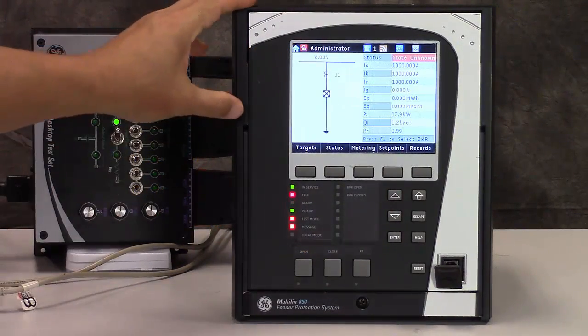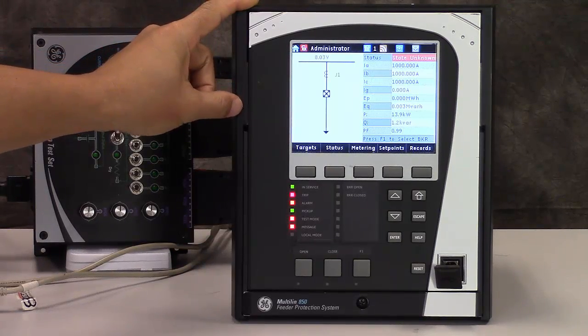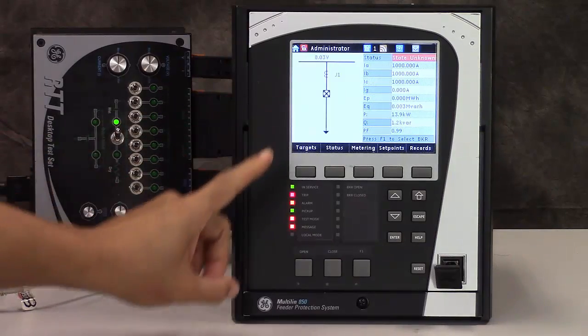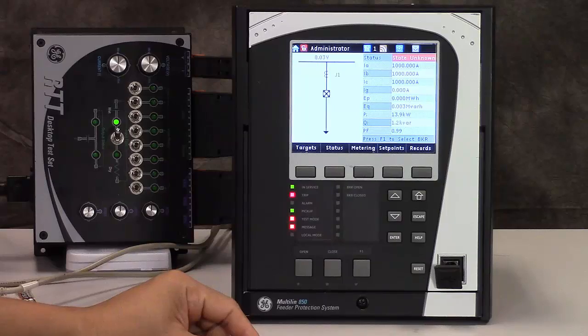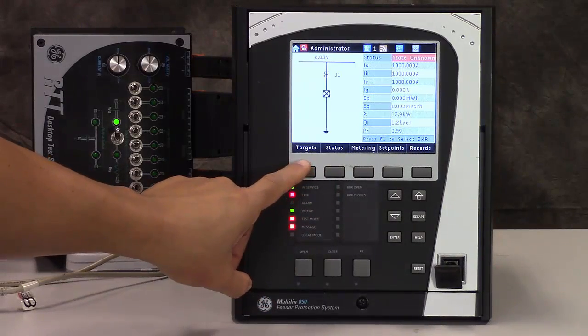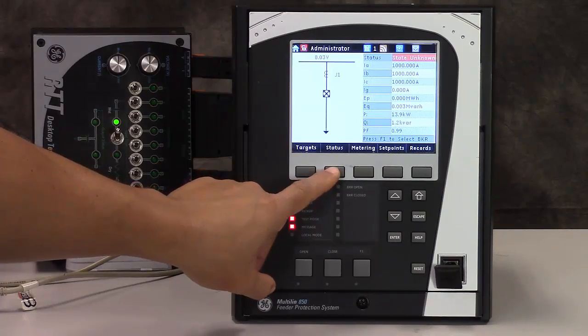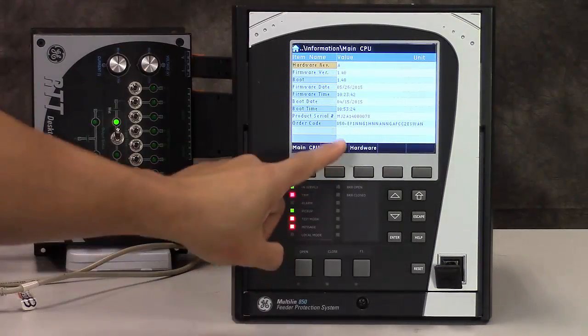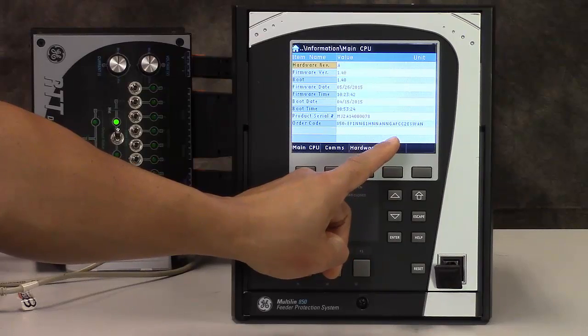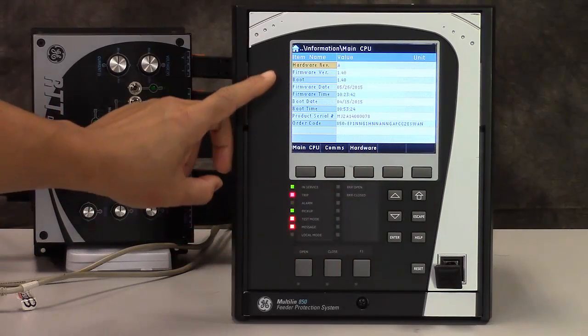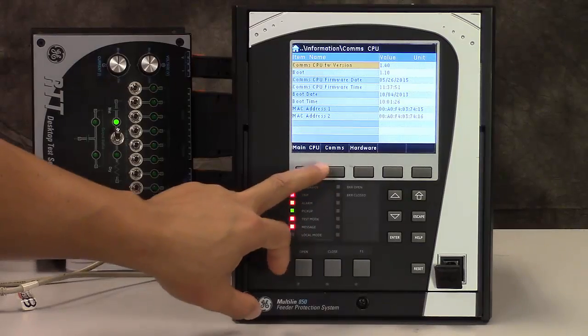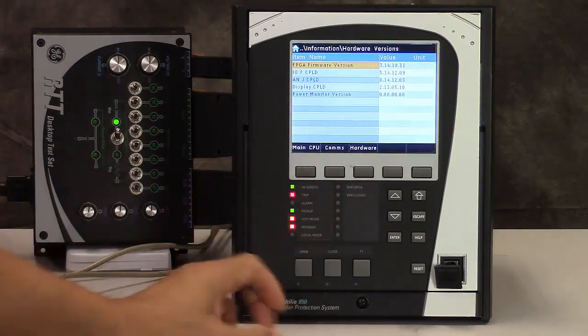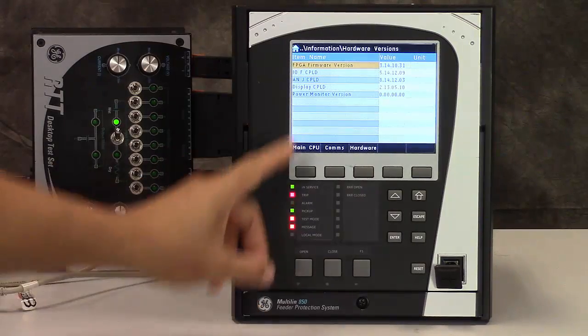Now we're going to explore the front panel of the 850 relays. From the front panel we can see the single line diagram and the metered current of the three phases. And at the bottom we've got the soft keys. We can check the firmware version by going to status, info, and we can know that this is the 850 relay. Secondary CT is 1 amp, and this has order code 2E, which means GOOSE messaging, 61850, is enabled. We can also know this firmware version is 1.4, and the serial number of the product. Also check the COM information like the MAC address and also the hardware, FPGA and CPLD numbers.